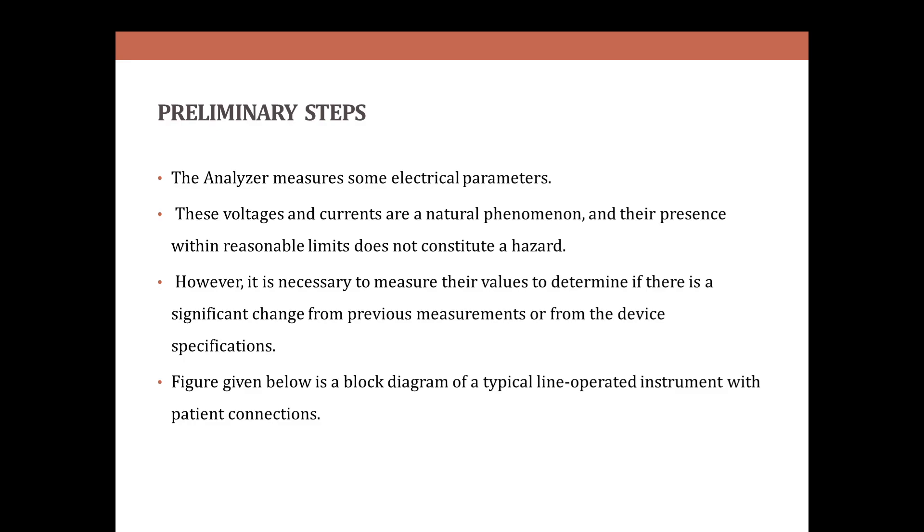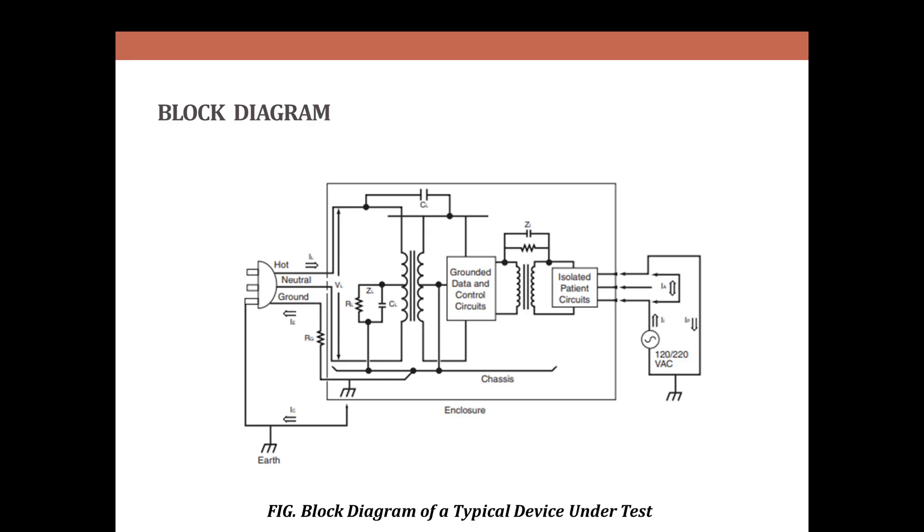We can determine the previous measurements or from the device specifications. The below figure shows the typical line-operated instrument with patient connections. This is the device under test which is connected with the analyzer. It is connected to the hot, ground and neutral connections. This is isolated patient circuits and grounded data and control circuits connected via resistors and inductance.